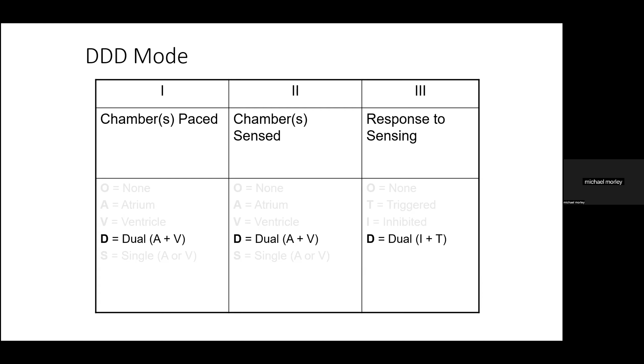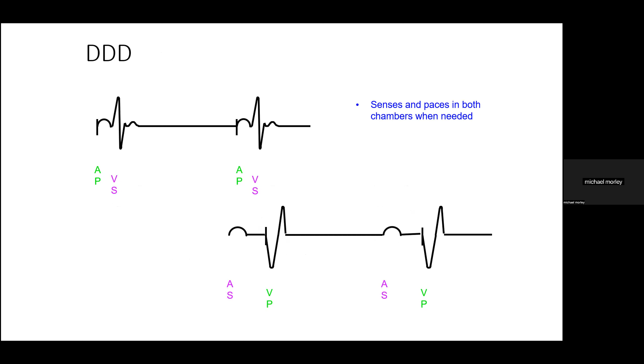In that way, we can get an A pace followed by intrinsic conduction and V sense, or we can get an A sense followed after a fixed delay by a ventricular pace. You can also have A sense, V sense, and you can have A pace, V pace. So there are 4 different ways in which the device can function. But the ultimate goal is maintaining AV synchrony and only pacing when required.